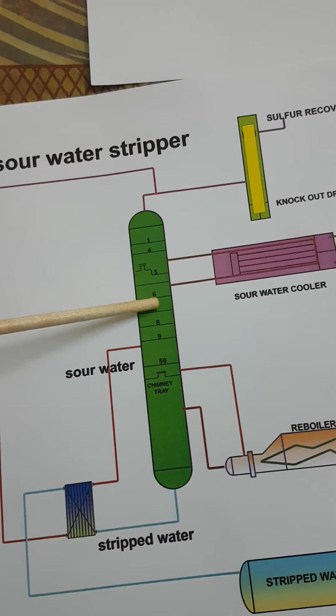So in a stripper, sour water will come here. Then whatever hydrogen sulfide is liberated or segregated will go up, and the strip water will get collected at the bottom. After that, the hydrogen sulfide gas which has been separated will go to the top section, and the bottom will be strip water. So from here the gas will go to the sulfur recovery unit. This was about the stripper.